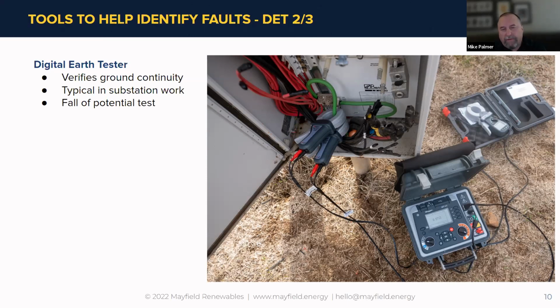But in the forefront picture, there's the big box, and then you see two clamps there. Those two clamps are that clamp-on earth tester, right? They come in that kit, and they become a clamp-on earth tester because the kit has a current and voltage probe. So that's all a kit. That's our all-in-one ground tester. Typically, that was created a few years ago for the filtering that's needed in substations because of the noise. But it's also all of our ground testers in one.